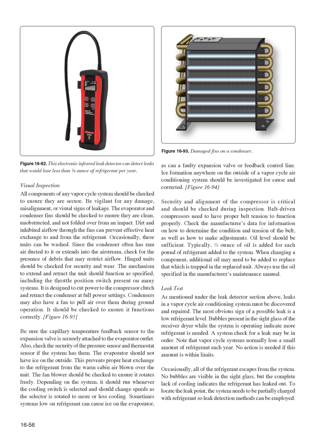Visual inspection. All components of any vapor cycle system should be checked to ensure they are secure. Be vigilant for any damage, misalignment, or visual signs of leakage. The evaporator and condenser fins should be checked to ensure they are clean, unobstructed, and not folded over from an impact. Dirt and inhibited airflow through the fins can prevent effective heat exchange to and from the refrigerant. Occasionally, these units can be washed. Since the condenser often has ram air ducted to it or extends into the airstream, check for the presence of debris that may restrict airflow.